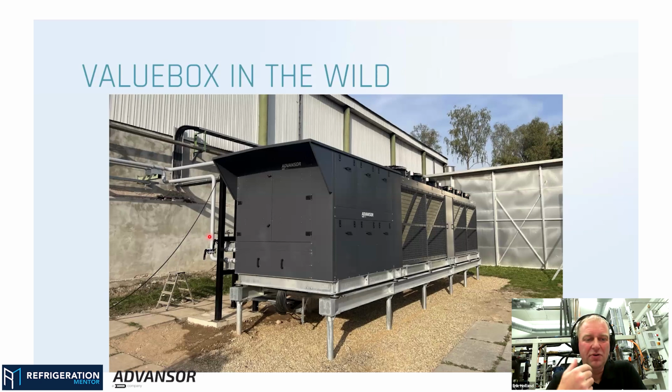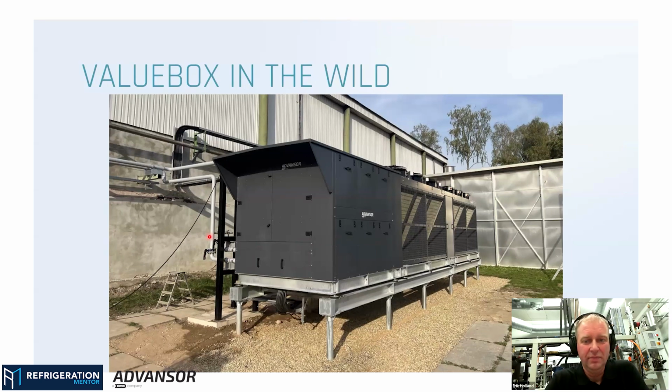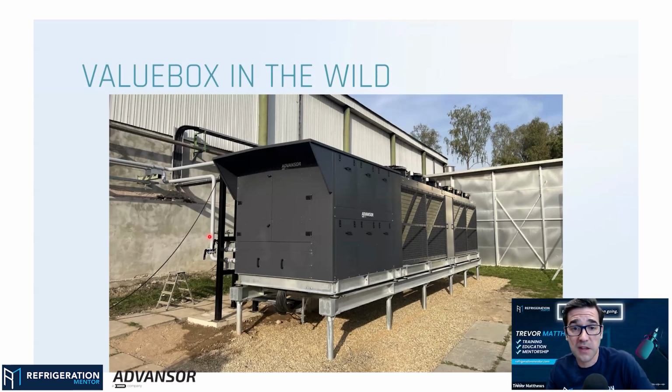And if you can't get that temperature, you have to do the vacuum for quite some time, and you have to rely on your crankcase heaters in your compressors to generate some heat for the system so we can boil off any moisture. And you may have to tarp it off and hire a heater. I've seen this happen in the middle of winter: they pull a vacuum, get big tarps and put them over the unit, and get big heaters blowing in on it to heat it up if it's so cold. You might not have done it before, but I've seen contractors have to do it.